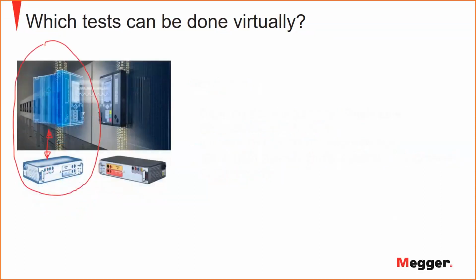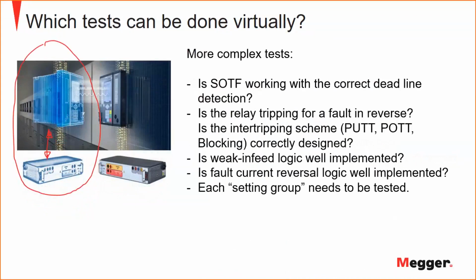Then you can do, of course, more complicated tests. Is switch on to fault working? Yeah, switch on to fault is a tricky situation. You have some settings, undervoltage and no undervoltage, circuit breaker connection, etc. It can be a tricky configuration. Test it and use a disturbance recorder to verify if it worked correctly. Is a relay tripping for a fault in reverse when you should not, or you should? Is the inter-tripping scheme correctly designed? Permissive underreaching, permissive overreaching, blocking? All of these things are based also on the fact that you open the event recorder and you look at the results.